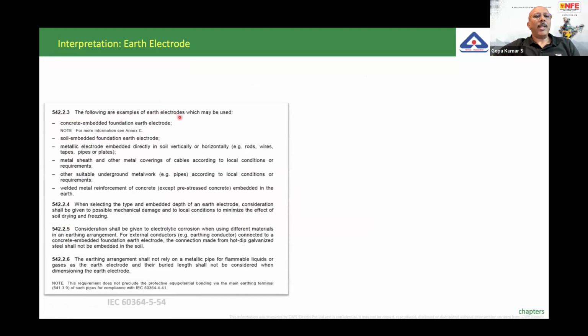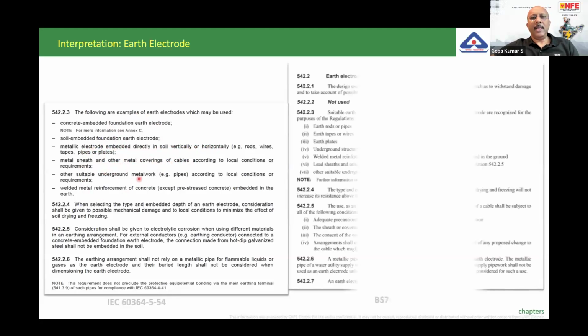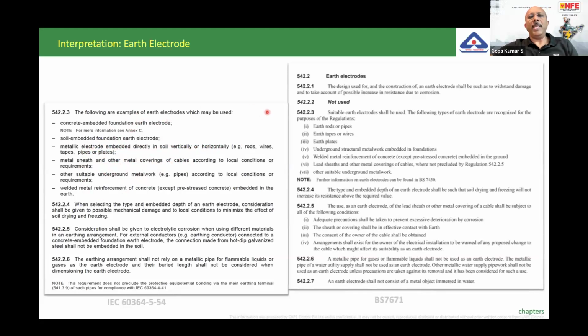Here you can see the IEC says the following are examples of earth electrode which may be used: concrete embedded foundation, soil embedded foundation earth electrode, metallic electrode embedded directly, vertically or horizontally, and of course, for smaller buildings, metal sheath or other metal covering. So basically there is a detailed explanation in the IEC. The same IEC has been adopted as BS 7671, including the article numbers, for example, 542.2.3. So 542.2.3 of both IEC as well as the British standard explains the earth electrode.